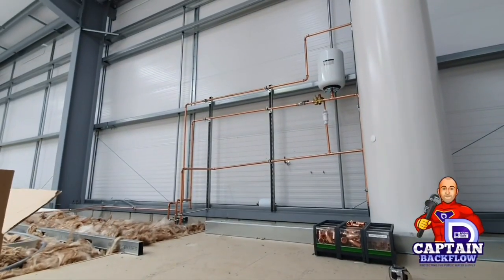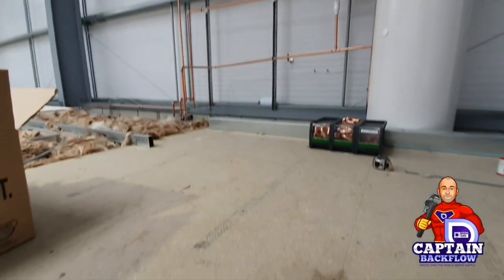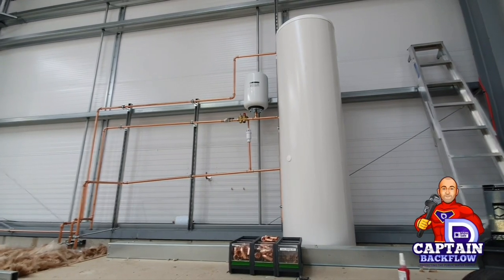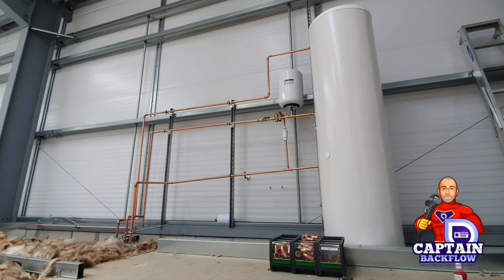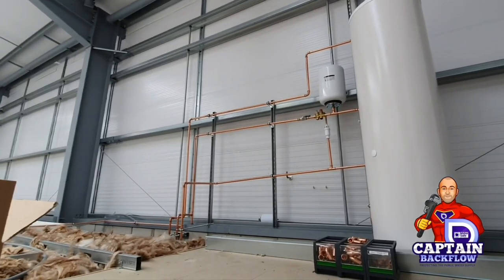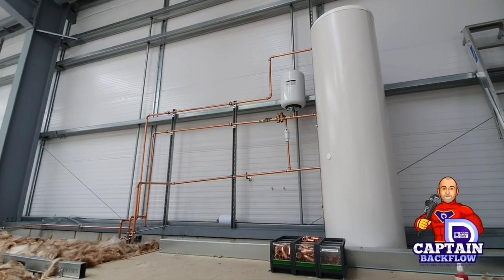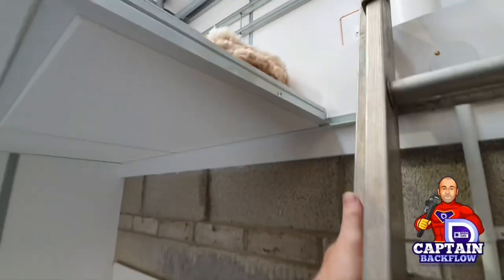We're now going up onto the roof above this toilet block to a little mezzanine area where we've been installing the unvented cylinder. I haven't got a finished photograph but you can notice the expansion vessel is in line in the pipe rather than using the flexible hose — we've done it that way because it reduces dead legs and allows a bit of water change within the expansion vessel.